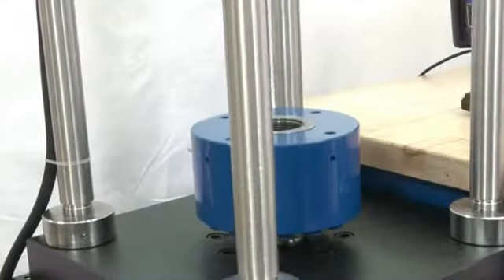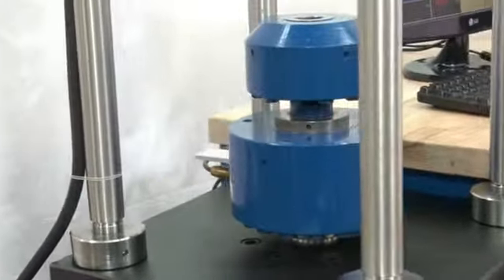As we assemble the load cell stack, the control and reference standard load cells are installed first. It's possible to use only one dual-bridge load cell for the control and reference functions, but having a separate standard cell is recommended.